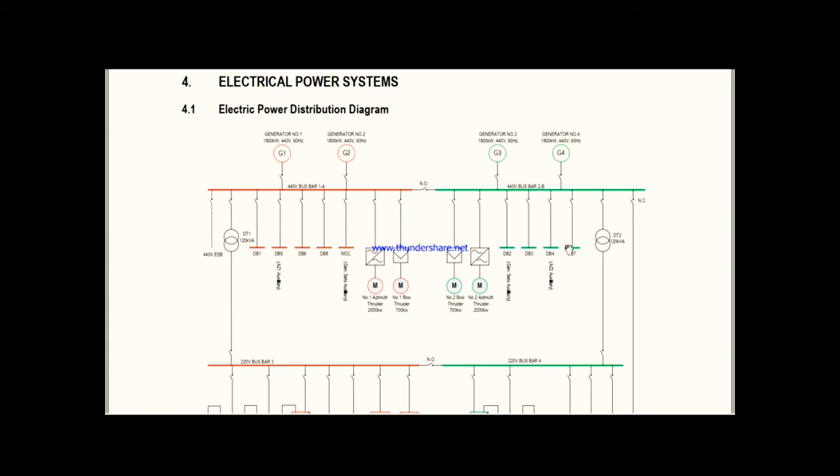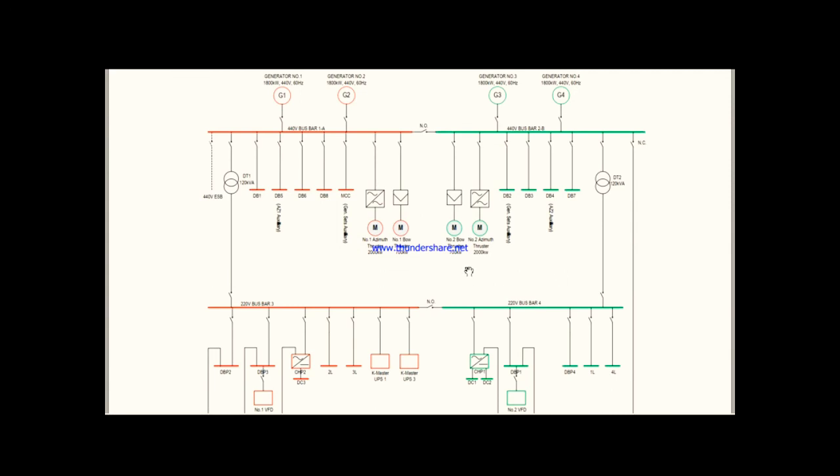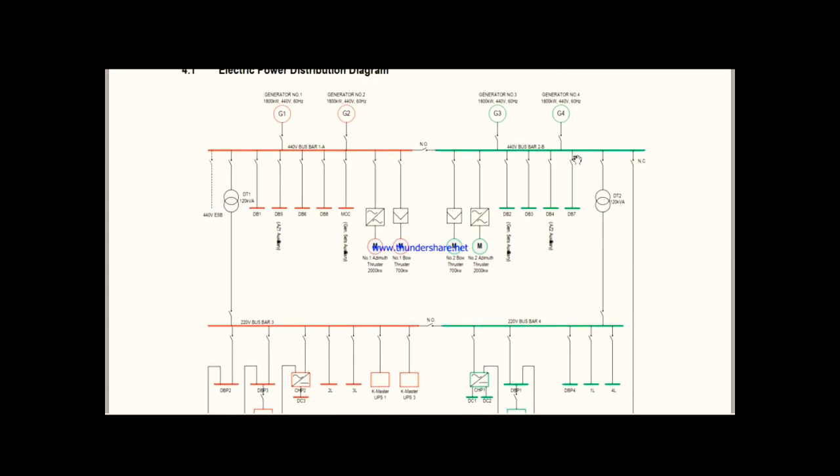You can see that both sides of the bus bars are similar, and in the middle there is a bus tie circuit breaker used to split or join the two bus bars. Suppose we are not in DP mode and need only one generator for all consumers — we can close this breaker, switch off two or three generators, and use one generator to supply power to all consumers if the load is light. Whenever you are sailing, you need generators on both bus bars. Now you understand what 440V bus bar 1A and 440V bus bar 1B are.